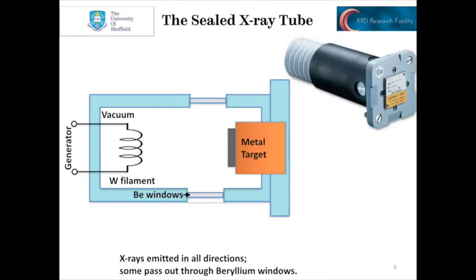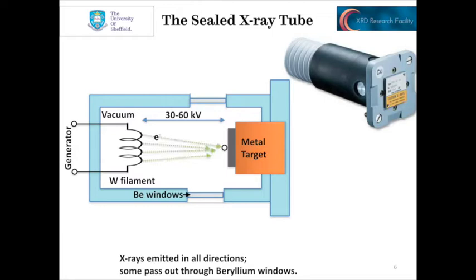Here we see a schematic and a photo of a sealed X-ray tube — the most common source of X-rays in labs around the world. In the top right, we see a picture of a ceramic sealed X-ray tube. Traditionally, the bottom part — the white section — would have been glass, but in recent years it has been replaced by a ceramic piece, making these tubes more reliable. On the left-hand side of the schematic, we have a tungsten filament, which generates an electron beam accelerated towards the metal target using a high potential of 30,000 to 60,000 volts. The electrons impact onto atoms in the metal target, causing the generation of X-rays, which are emitted in all directions, some of which pass out through beryllium windows.